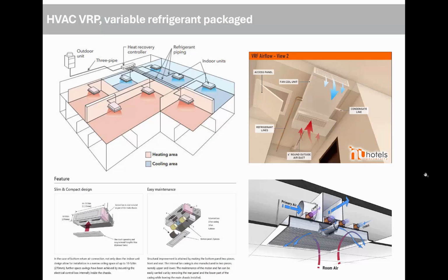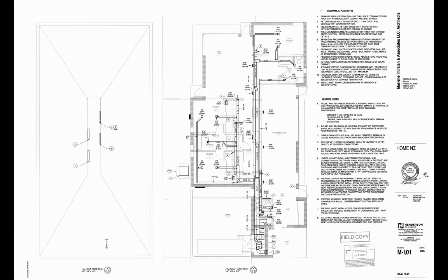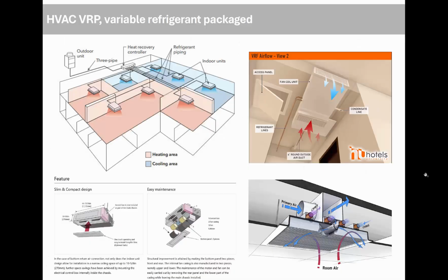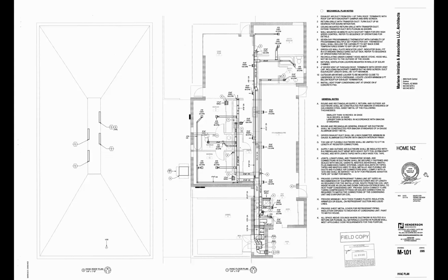And you can see below that a couple of examples of the design, right? Sort of a transparent view of that unit being inset with the return and supply air, and another one below that. This is just a quick plan of a Revit HVAC model. And so you can see in Revit, you can actually go in and put in all of the ducting at the actual size. One thing we talked about, and you can see in these, is that you have the supply and return all sort of in one space here. In this particular installation, the mechanical room is here, so you have your fan coil unit here, right? And then your outdoor condensing unit here.